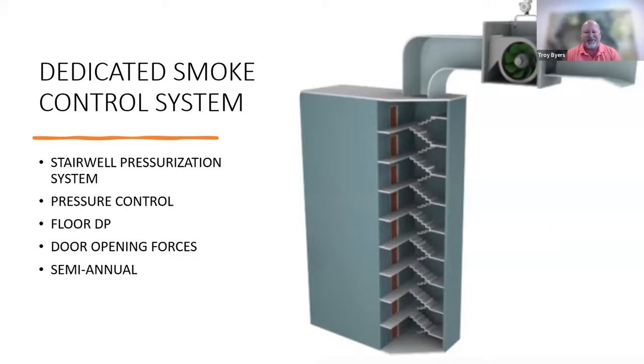So that's going to be my next point. This is dependent on your code and your authority having jurisdiction. Your local code is going to take precedence on that. Ultimately, what we're trying to do is keep the smoke out but allow occupants egress through those doors. So we're going to measure door opening forces in three different components.